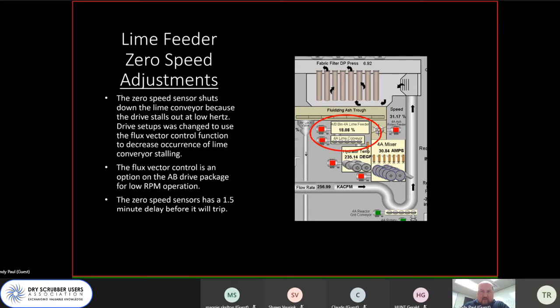A big thing for us was the lime feed zero speed adjustments. Like most coal-fired power plants, we're living the new life of cycling load, and when we have low loads, we often could not inject lime low enough without tripping out our lime feeders. So we had additional usage that we didn't need for SO2 control simply because we couldn't get the feeders to run down low enough. What we did to combat that is there's a drive package for low RPM operation. It's called a flux vector control.